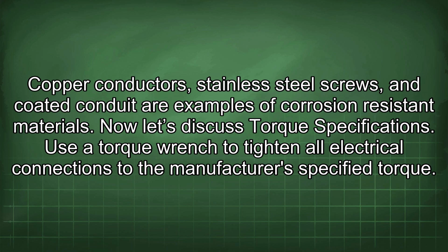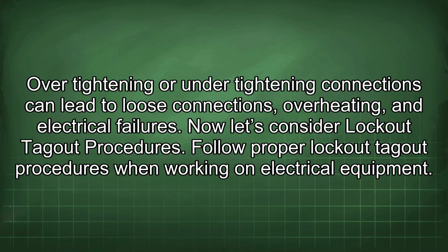Now let's discuss torque specifications. Use a torque wrench to tighten all electrical connections to the manufacturer's specified torque. Over-tightening or under-tightening connections can lead to loose connections, overheating, and electrical failures.